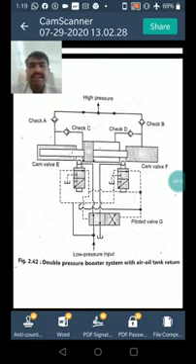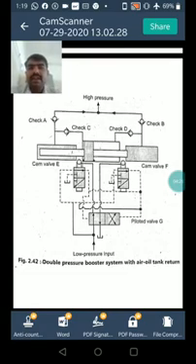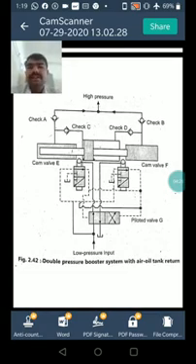In step 1, valve A is actuated. The air is directed to the approach tank. Oil from the approach tank is forced through the booster cylinder to the head end of the working cylinder. This is a low pressure approach stroke. Then step 2, valve B is actuated. The air is admitted to the head end of the air cylinder and it increases the pressure in the booster cylinder oil, and thus the high pressure short stroke of the working cylinder takes place.